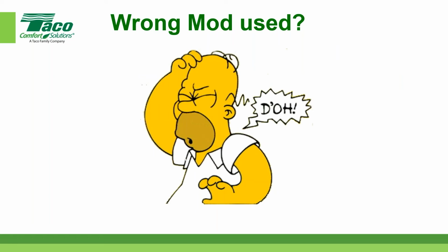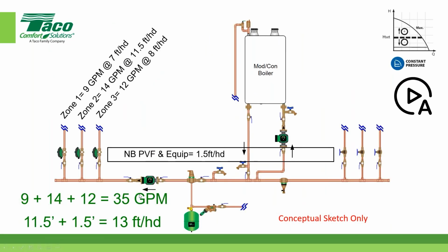Okay. All right. So what happens when we choose the wrong mode of operation? Notice I've given some numbers here, and this is purely hypothetical: 9 GPM, 14 GPM, 12 GPM. I'm staying with the 3 zone because I want the picture to be big enough. This could be multiple zones out here, but let's say that we need 35 gallons a minute, and at 35 gallons a minute during a design load condition, I'm going to be at 13 foot head. You can see how I got that information by adding these numbers up. That's all given here and up here. So this pump, this system circulator, needs to give me 35 gallons a minute, 13 foot head.